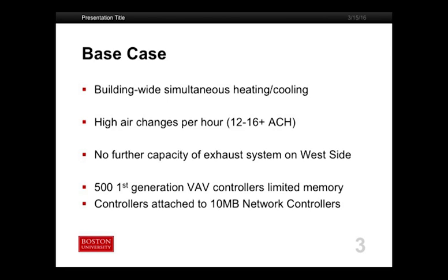Our air changes — I didn't want to be too embarrassed up here, Tom, so I dumbed it down to 12 to 16, but I'll add a plus, since we might be up to 24 in certain areas. What really happened is that over time, as we switched from electrical and electronic labs to wet labs, we lost exhaust system capacity on half the building.